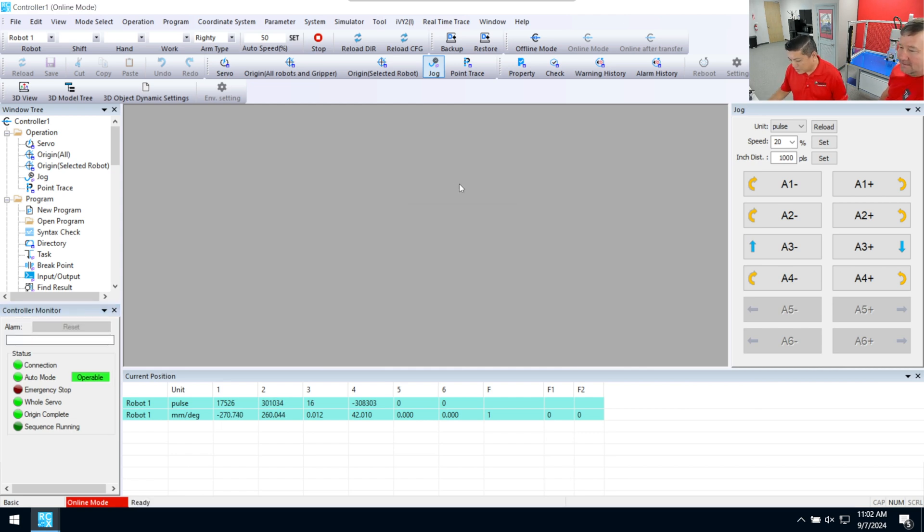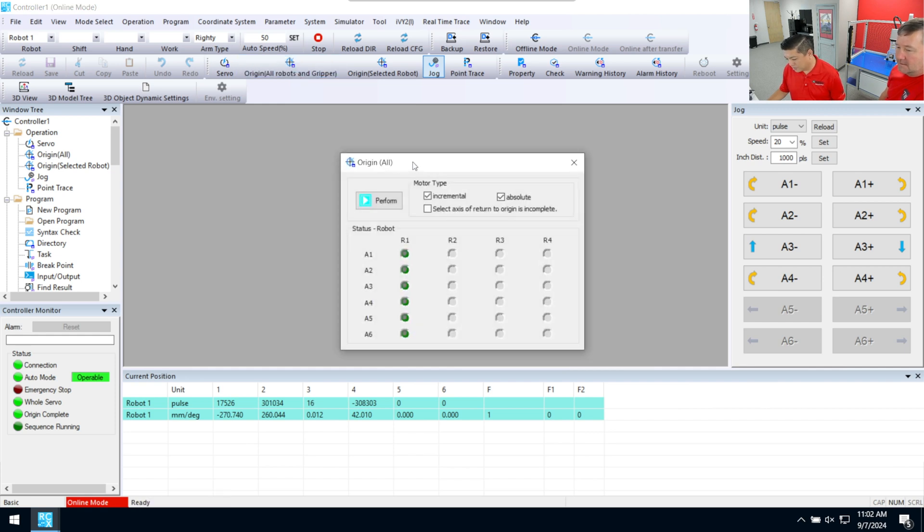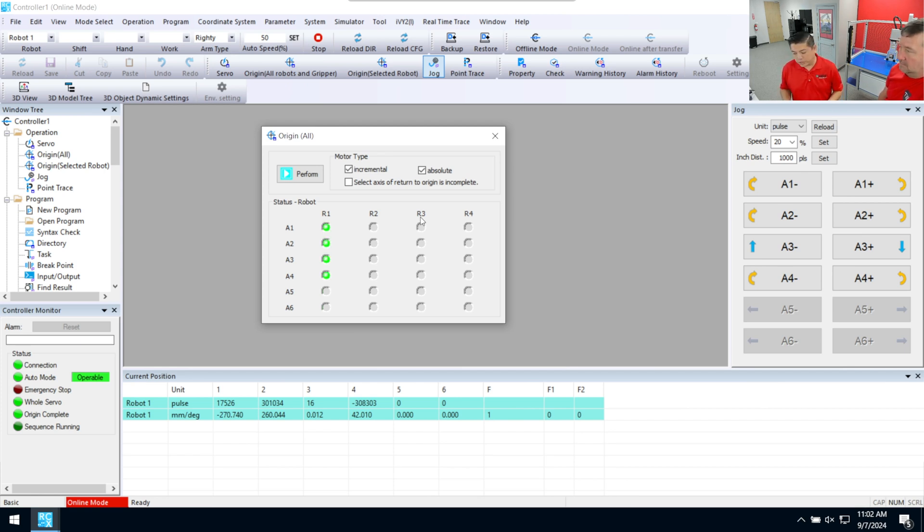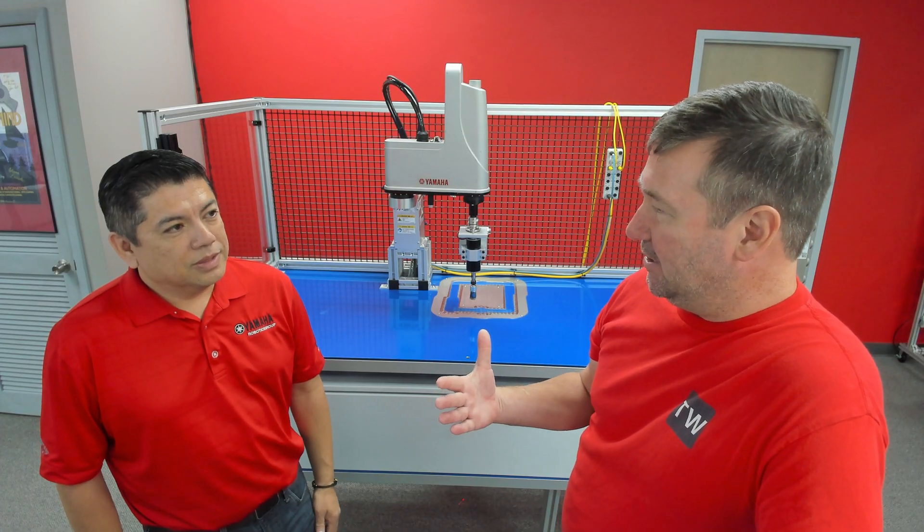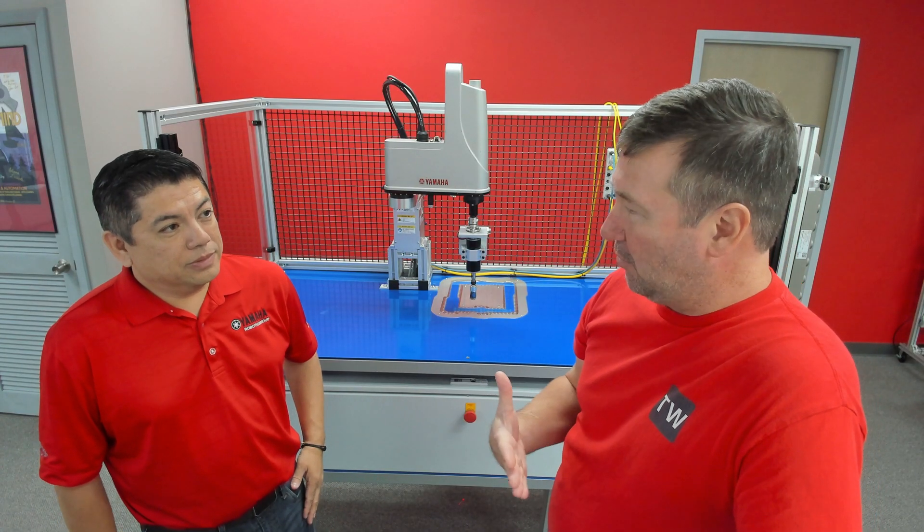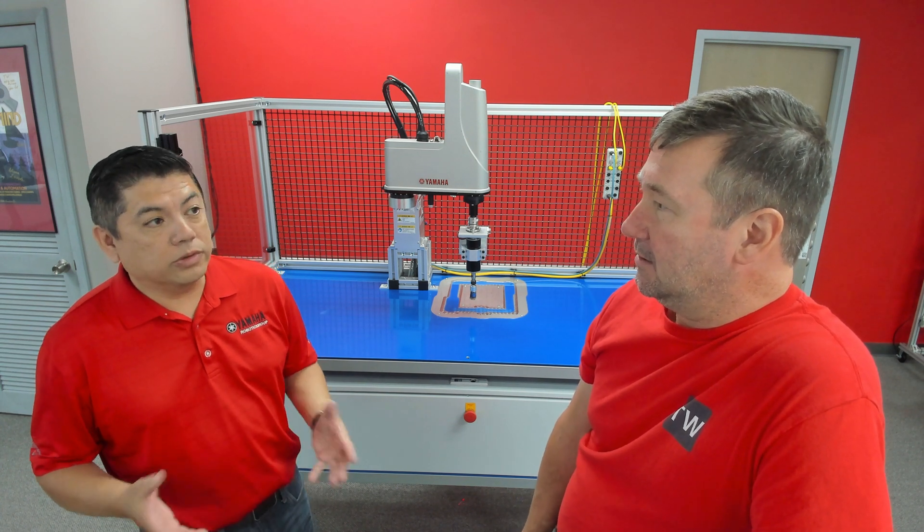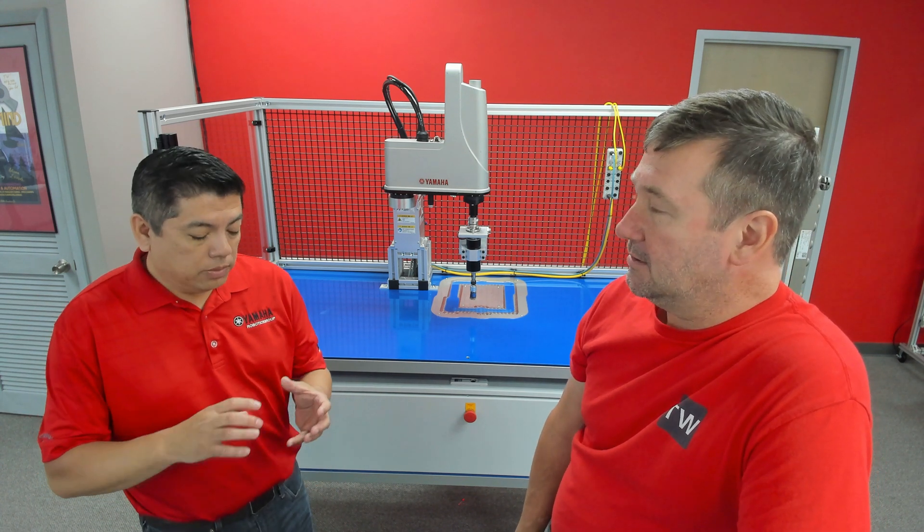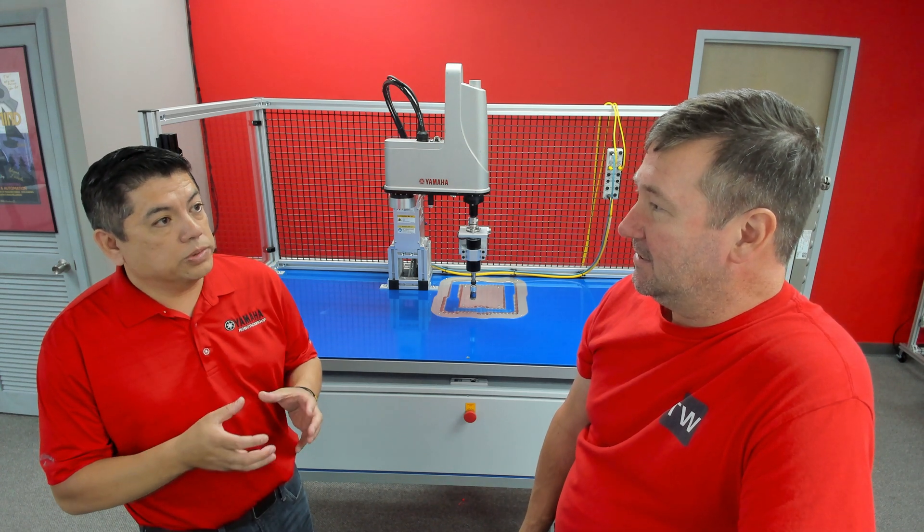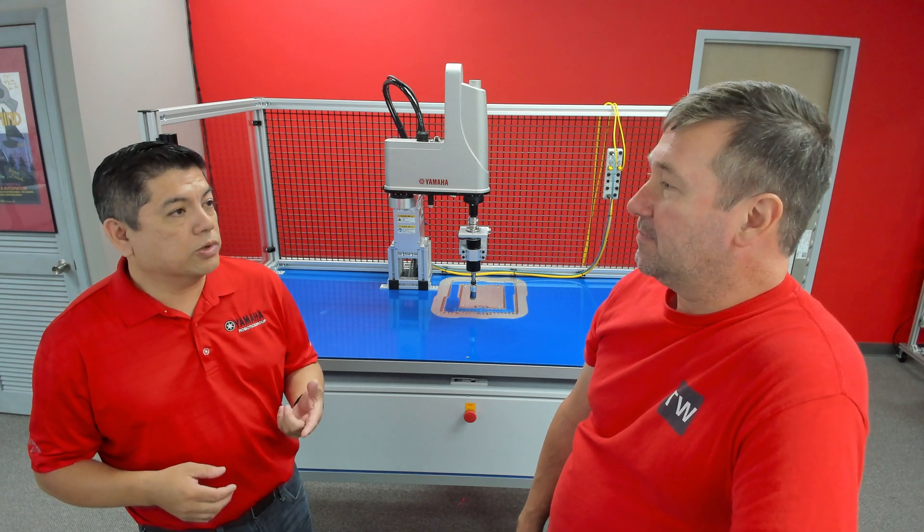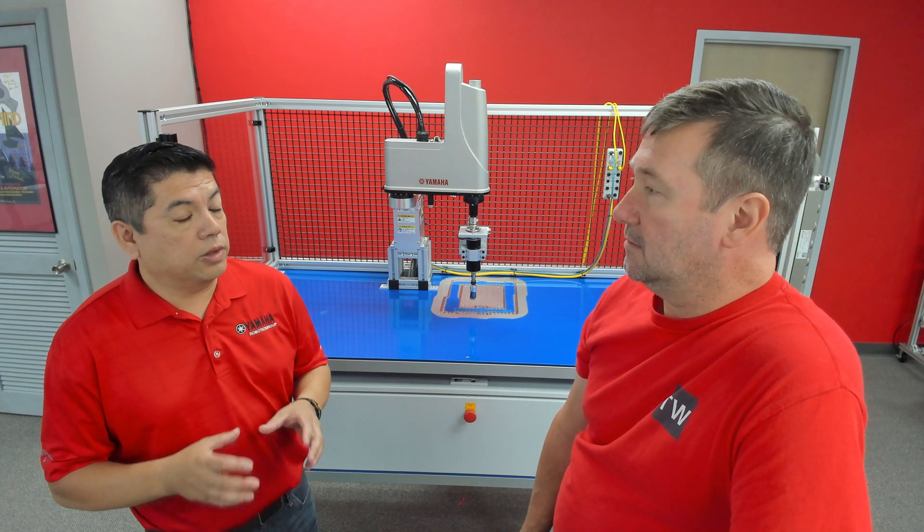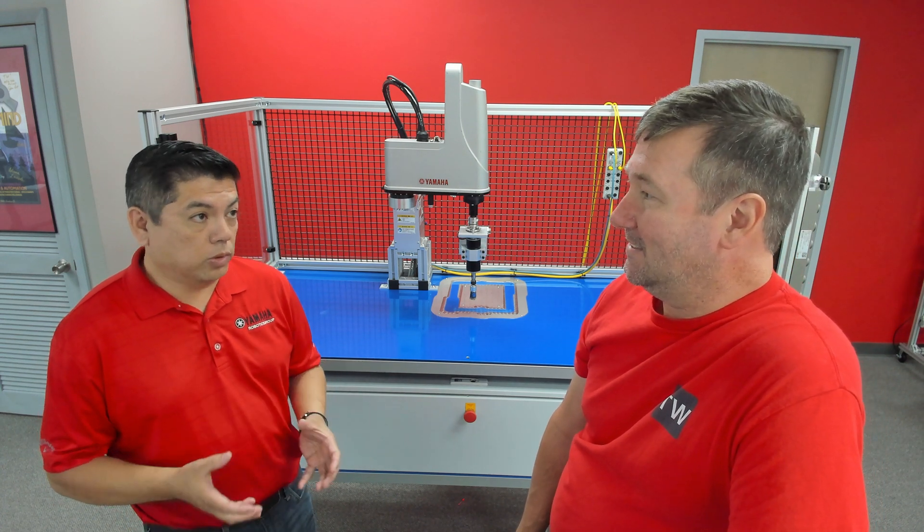So we've already turned on our servos and the next step is to origin all of our axes on our robot. So out of the box, normally the robot hasn't been origined. It needs to be origined for the first time when you take it out of the box. And when you say origin, what exactly are you doing? Is that for like homing the robot? Is that what that means? Yeah. So it's the same thing as homing like a regular servo motor. When you first power up a servo motor, it needs to go to either a torque or a sensor home. And that establishes a zero position.